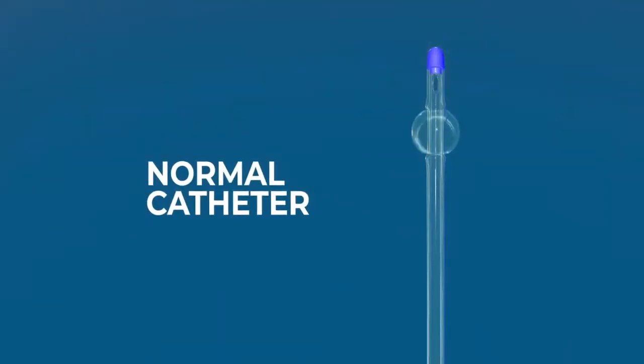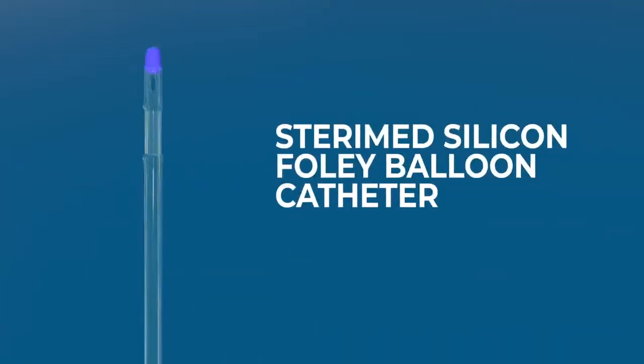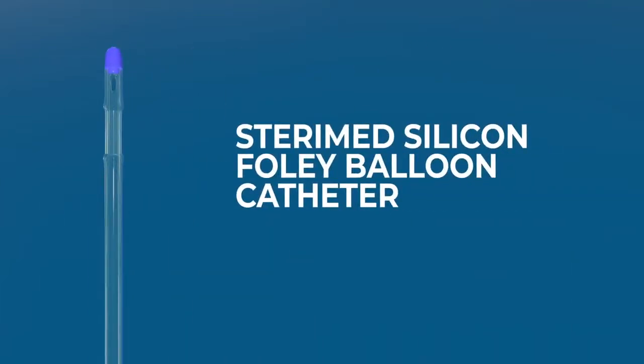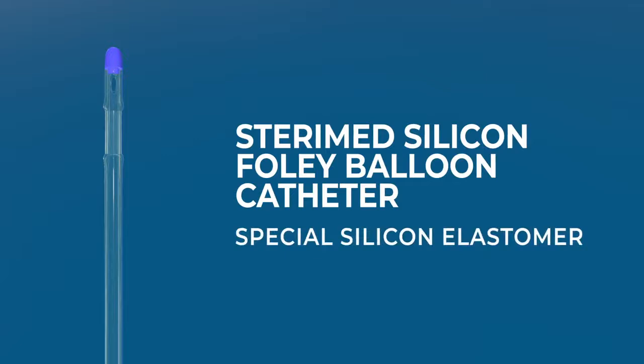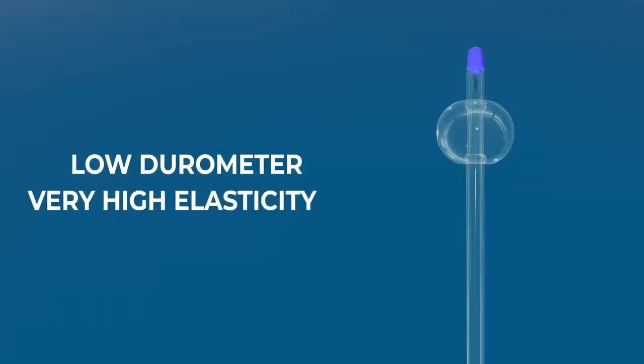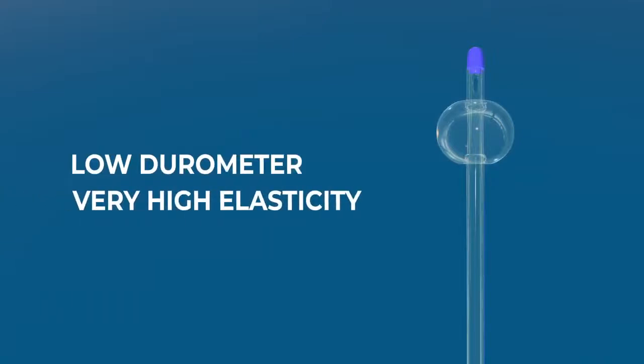Normally, a lot of silicone catheters have a major problem of balloon tearing after inflation in the bladder. The Sterimed all-silicon Foley balloon catheter uses a very special silicone elastomer to make the balloon. The elastomer has a very low durometer and a very high elasticity.